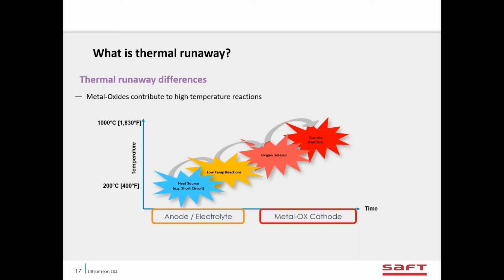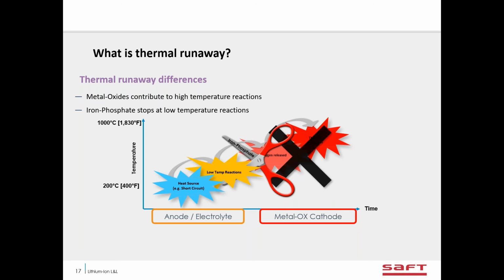And that often can lead to propagation within a module or within a cabinet, where one cell goes into thermal runaway. It gets so hot that it starts the one next to it, and then it becomes a domino effect through the battery. But with iron phosphate, the oxygen is bonded chemically much stronger on the cathode, so that oxygen is not released into the thermal runaway condition. So iron phosphate cuts the high temperature reactions from happening, and we don't get the oxygen release in the thermal runaway at the very high temperature. So this is a big difference between iron phosphate and the metal oxide versions.